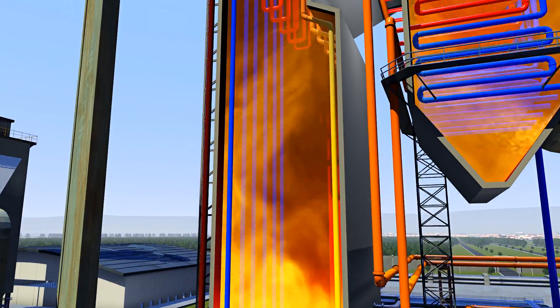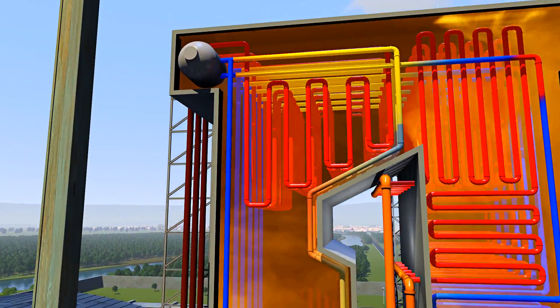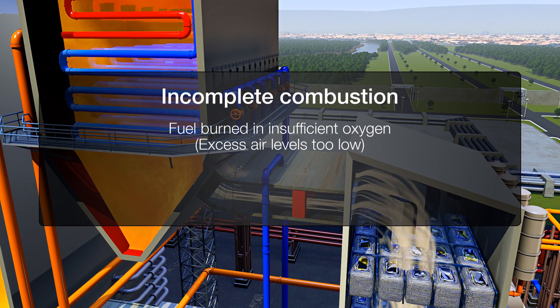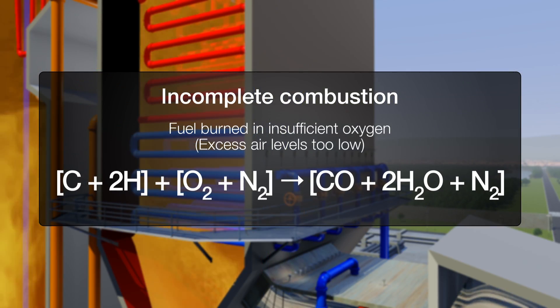Measuring for carbon monoxide provides an ideal means of compensating for these variations. Carbon monoxide levels will start to increase when the amount of oxygen is insufficient to allow complete combustion.